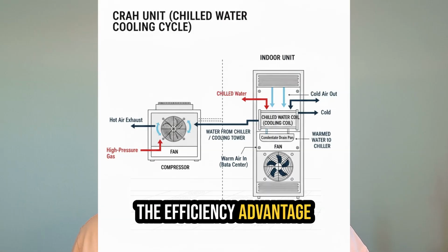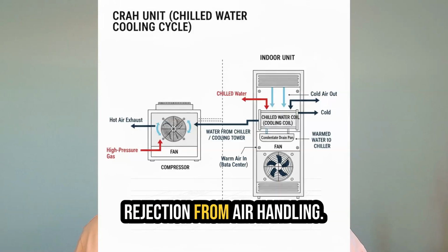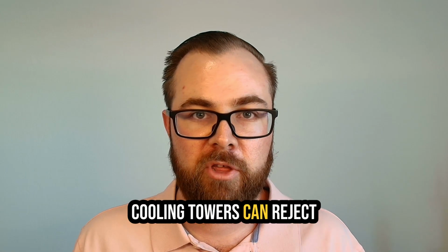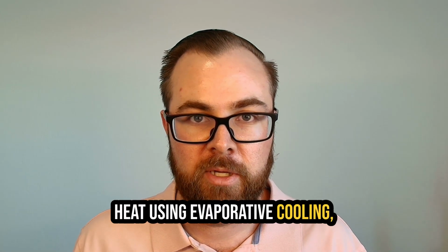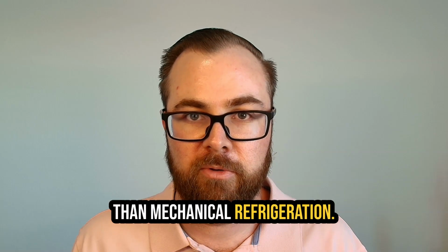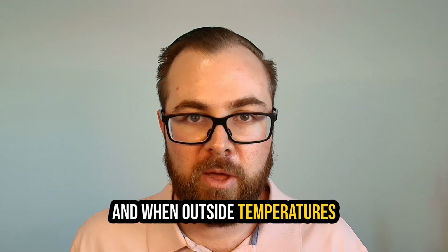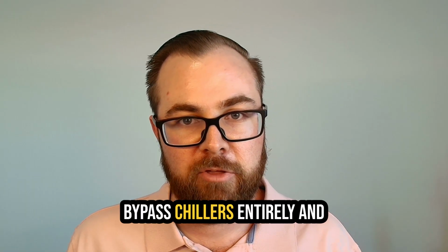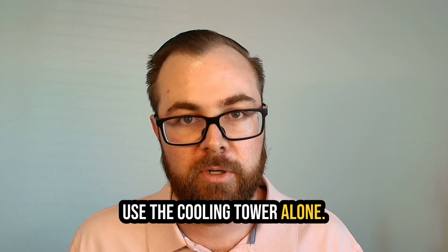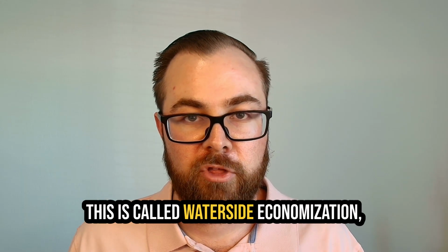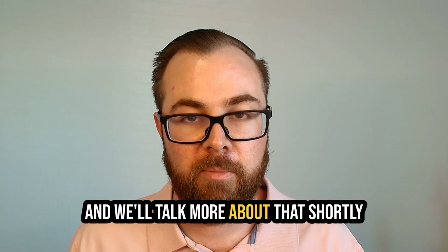The efficiency advantage comes from separating heat rejection from air handling. Cooling towers can reject heat using evaporative cooling, which is far more efficient than mechanical refrigeration. And when outside temperatures are low enough, you can bypass chillers entirely and use the cooling tower alone. This is called waterside economization, and we'll talk more about that shortly.